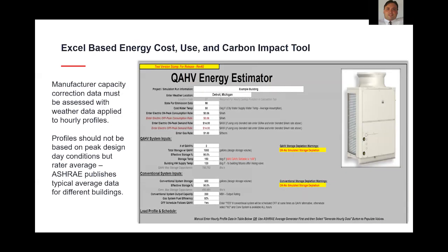In terms of assessing energy performance with these systems, you really have to start looking at manufacturer correction data, capacity data, and power input data. And we just illustrated that information previously on those slides when we looked at those three different operational modes. And then from that data, you can ascertain effective COP or EIR, energy input ratio. And then you really need to apply that to get an accurate assessment of savings to an average representative profile. And when I say profile, I mean a domestic hot water load profile. And then that has to be applied also with correct ambient conditions.